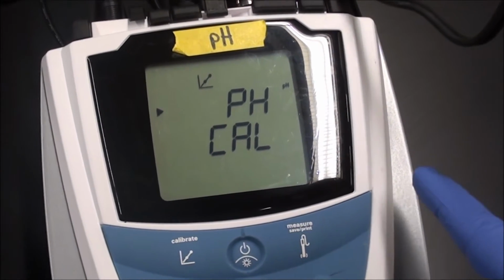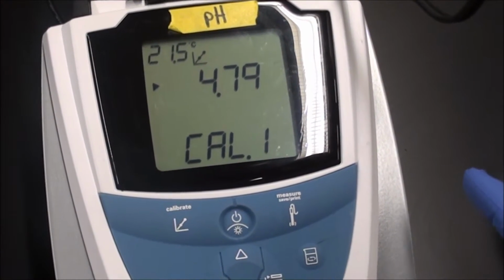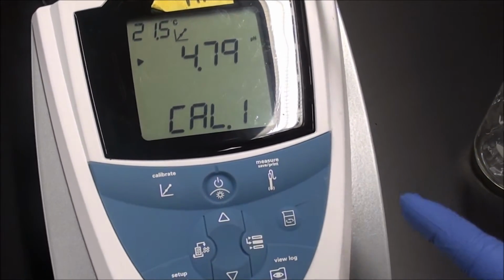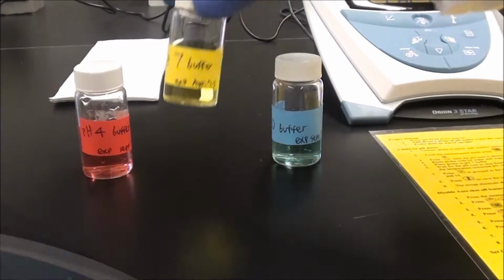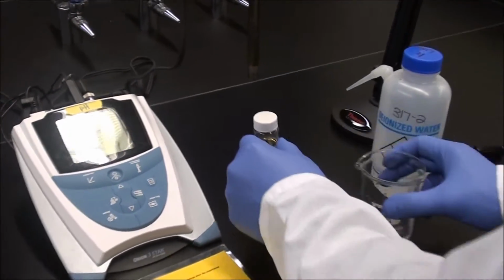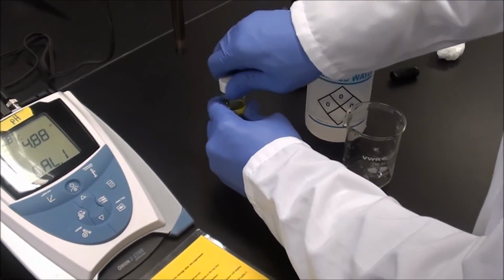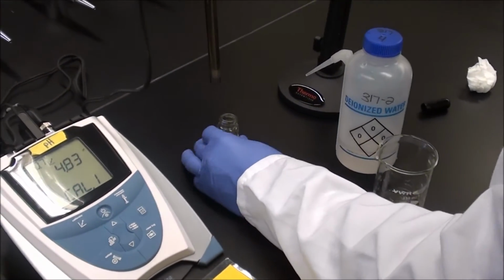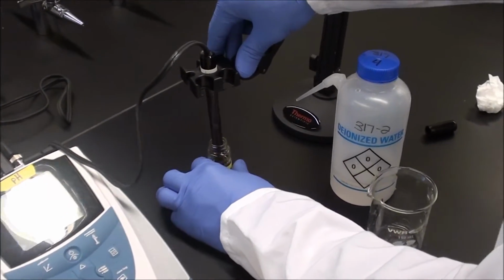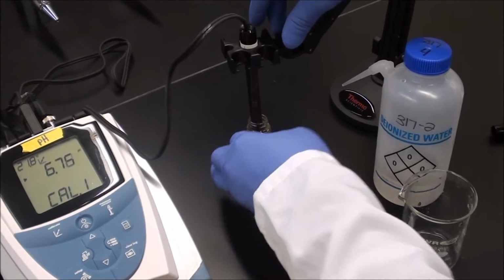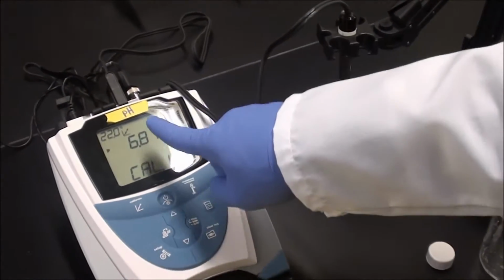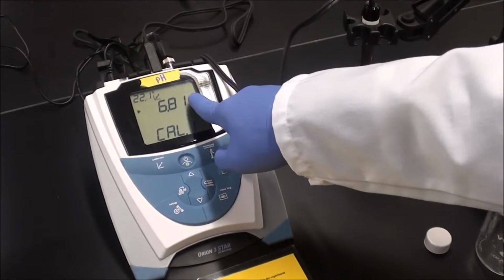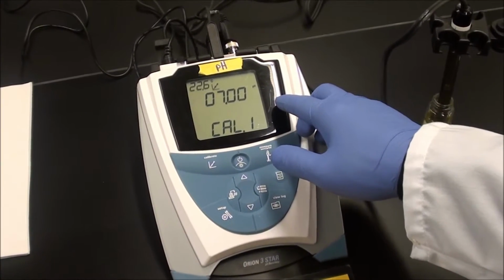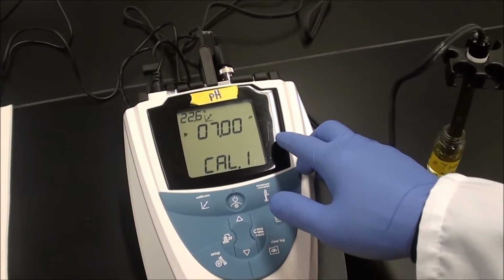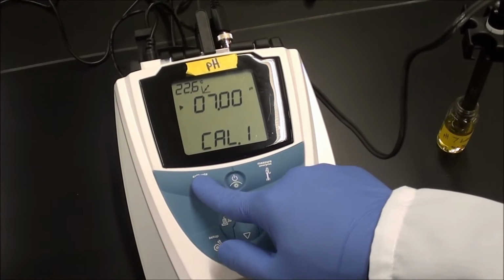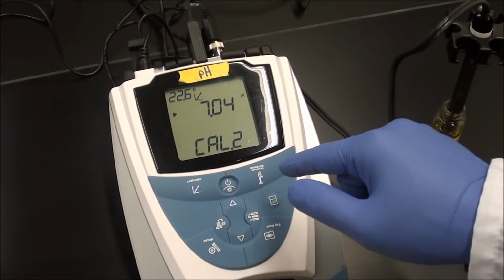We already rinsed our pH probe with DI, and then we wiped it with a Kim wipe. So now we're gonna go ahead and place the probe in pH buffer 7. Make sure to submerge it all the way down. And you keep waiting until the pH stops flashing. When the pH icon stops flashing, the meter will display the temperature corrected pH value for the buffer. You want to go ahead and press calibrate to proceed to the next calibration point.